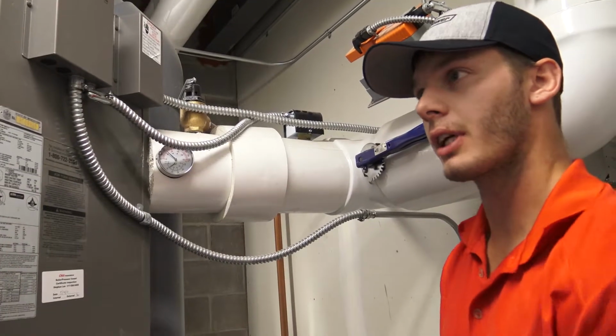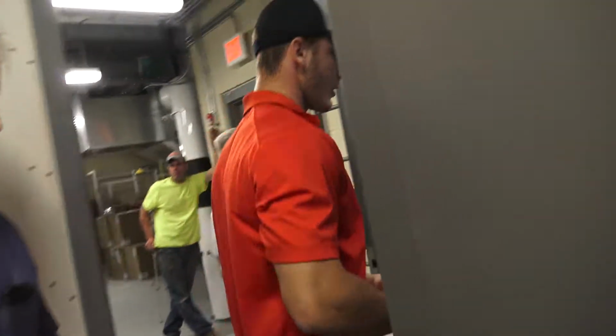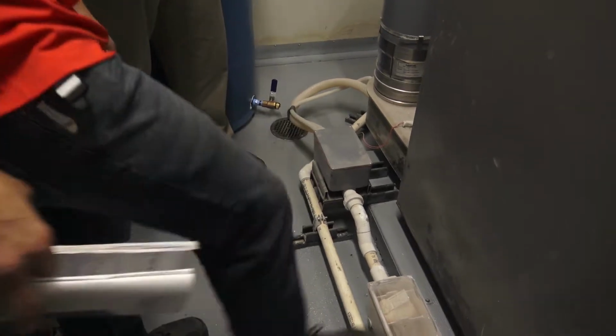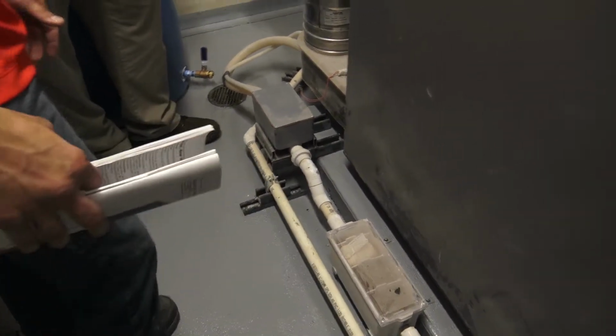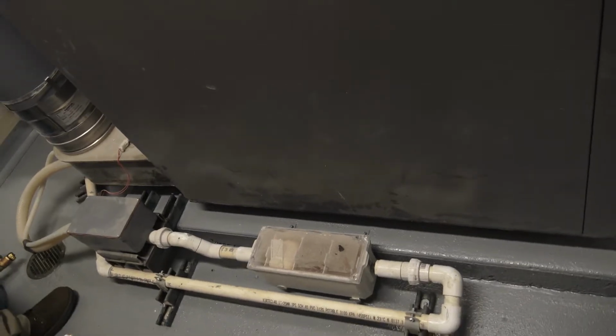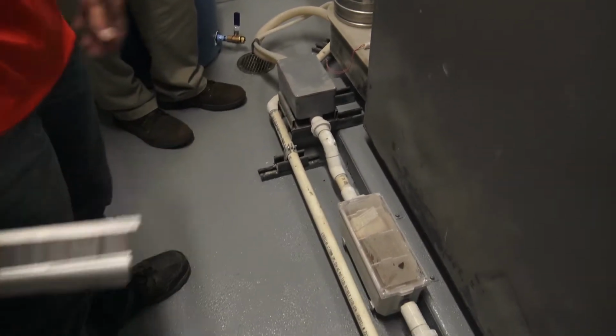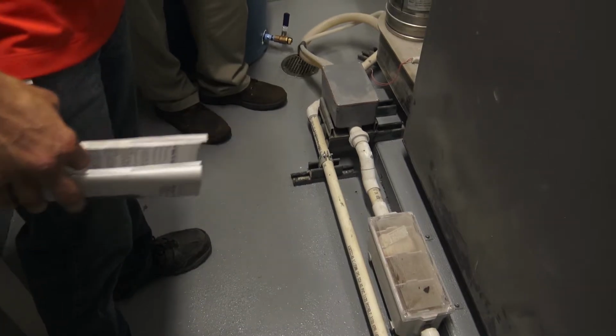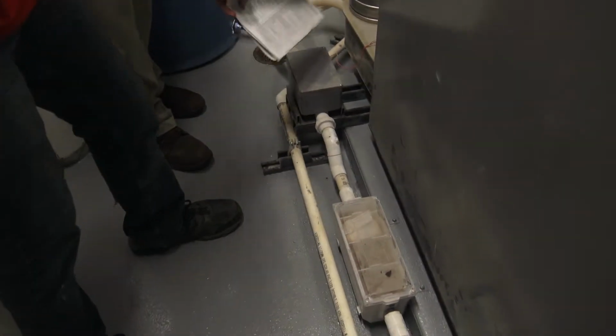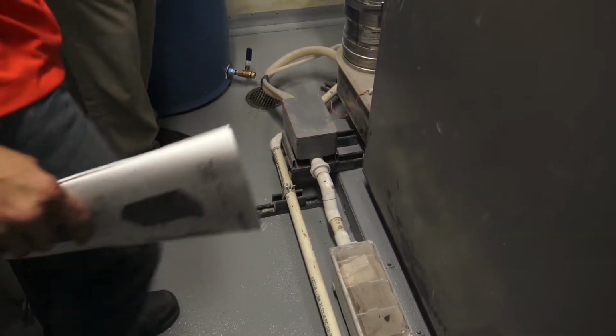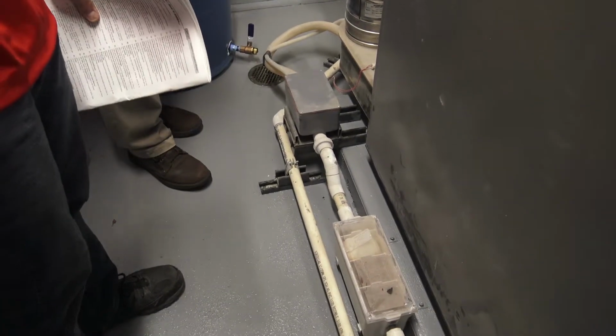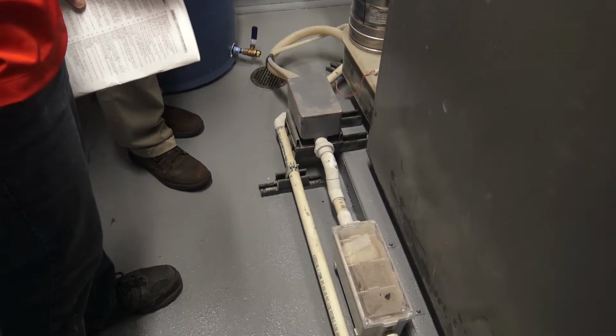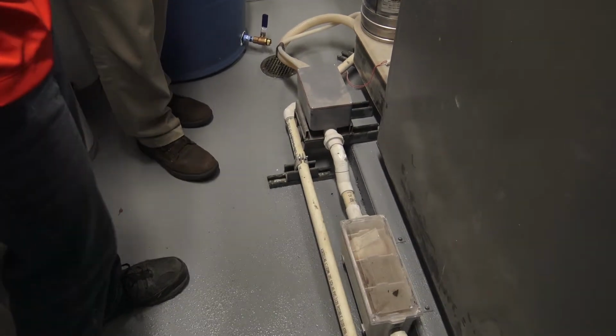Do you have any questions? Anybody? So yeah, there's this condensate trap or gasket or whatever you want to call it. We don't have that on anything else. Okay. So pretty much if your condensate were to get clogged up, what this does right here is this is your neutralizer. The water can come out a little acidic sometimes, so all it pretty much is, is this limestone. It's just going to bring the acidity of it down. There's a little float in here. If this gets clogged up at any point, you will get an alarm on the boiler that says condensate trap open, which means, okay, there's a possible clog.